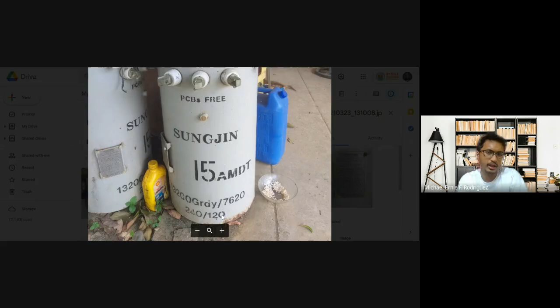We also have the voltage here: 13,200 volts GRDY, grounded Y, which is the line to line voltage, and 7620 volts line to ground. That's for the primary or high voltage side. On the low voltage side, secondary side, we have 240 volts line to line, 120 volts line to neutral.